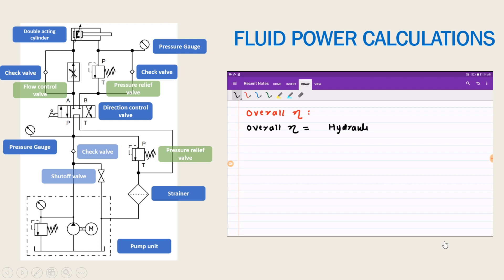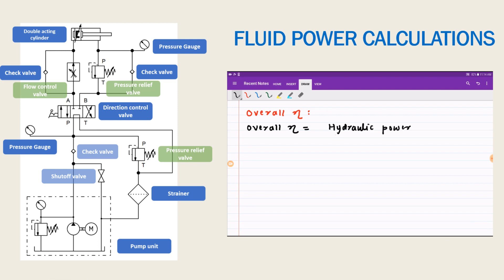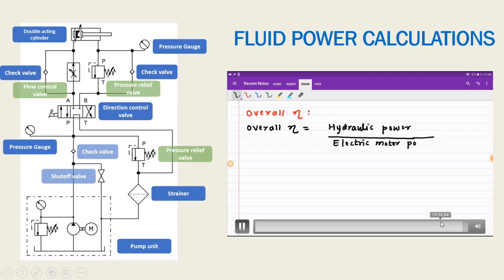Finally, overall efficiency is the ratio of output to input. Output is the hydraulic power and input is the electric power generated by the motor. The motor supplies power to the pump, so overall efficiency equals pump hydraulic power divided by electric motor power. In this way we can find out the fluid power in hydraulics and pneumatics.